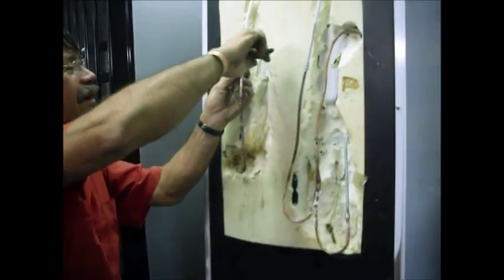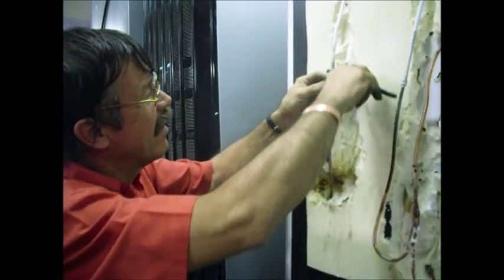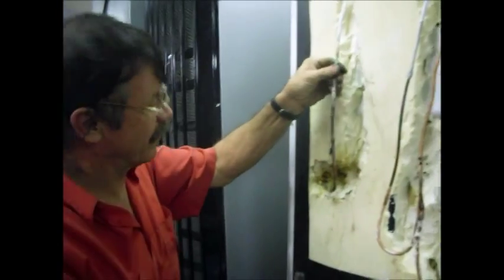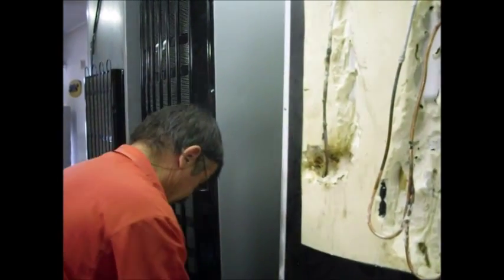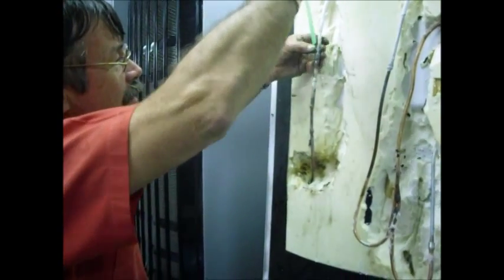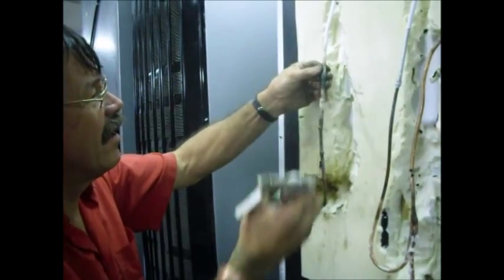It doesn't look like there is any leaks but the aluminium weld has got a bit of flux on. Let me just remove the flux because that could be covering up a hole. Putting some of this on in, we can confidently say there is no leaks.